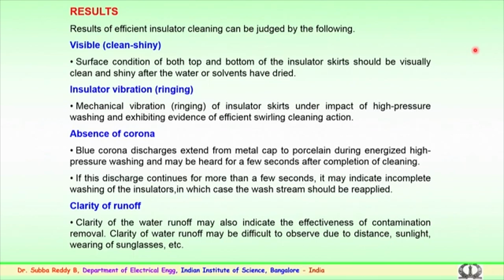Second is the insulator vibration or ringing sound. Here again is the mechanical vibration or ringing of insulator skirts, particularly the petticoats or sheds, as we call them for the porcelain insulator, under the impact of high pressure washing, exhibiting evidence of efficient swirling cleaning action. Based on experience, the personnel or technicians can feel the vibration or the noise of the high pressure washing on the surface or sheds of the insulators. This can also be noticed during high pressure washing as efficient cleaning action.